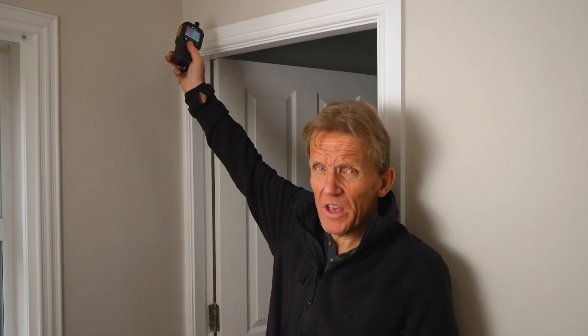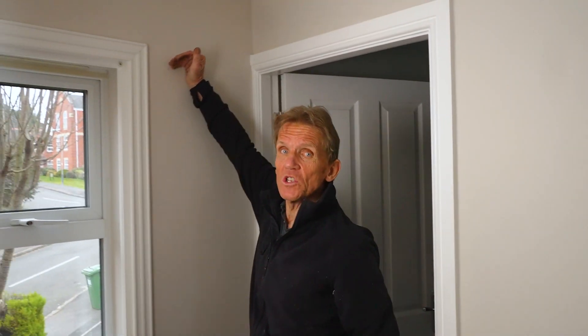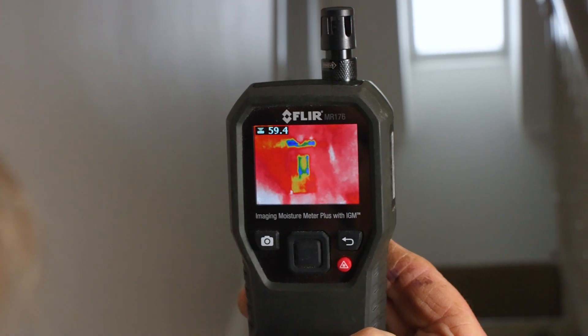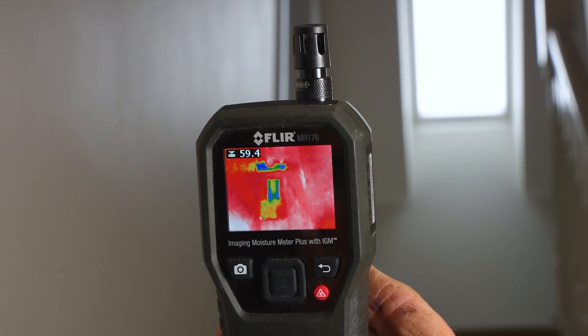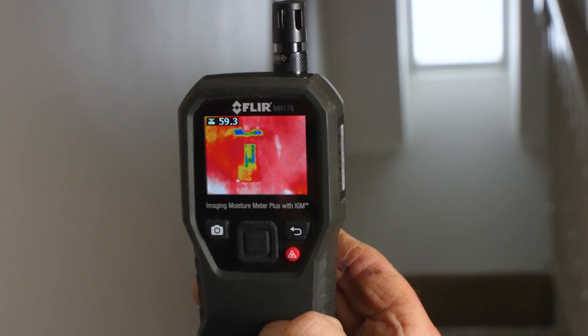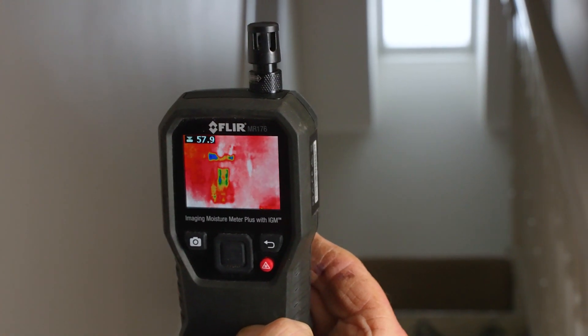What we're trying to find is best seen at nighttime when the sun's gone in and you have that contrast. What we're finding is it's along all the edges - all the way around the house - that top bit where the wall insulation finishes and the roof insulation hasn't taken over. There's a gap there. And there's a roof window - you'd expect that not to be as warm - but just above it, showing cold, there's a bit of insulation missing at that point.